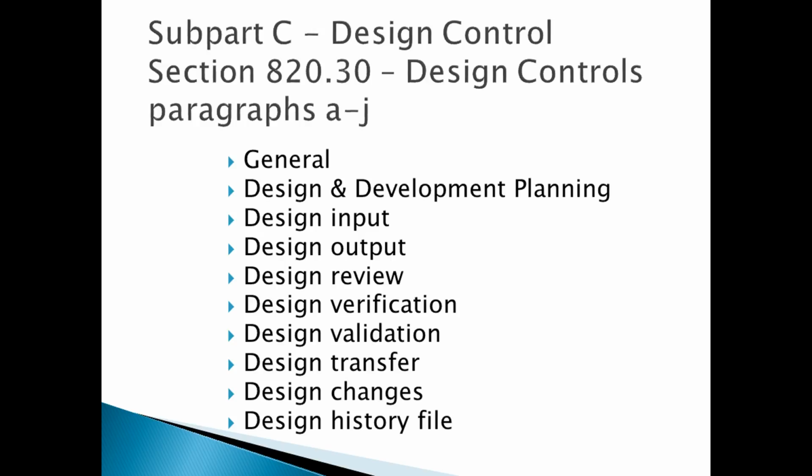so you can see their general provisions. You get into planning, design input, design output, review, verification, validation, transfer, changes, and design history files. So we have taken all of these design control elements and formulated our own standard operating procedures. And so what we do is we have the students follow the standard operating procedures, and it really mirrors the best case in industry. So all medical device companies have to follow design control, yet the federal code is actually pretty thin and describes these standards at a very high level.